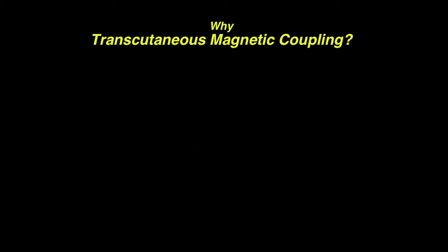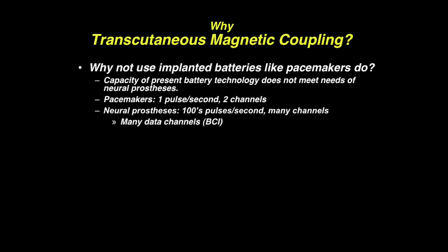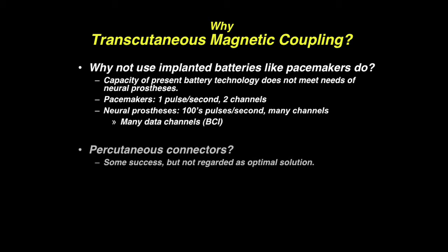Now, why do we have to do this? Why can't we just use implanted batteries like pacemakers do? The problem is that the capacity of present battery technology doesn't meet the needs of neuroprostheses of any kind. And the reason for this can be seen just by looking at numbers. Pacemakers typically will pace about 1 pulse a second, maybe a couple of channels. Neural prostheses, in order to communicate with the nervous system, may have hundreds of pulses per second and many, many channels or many, many output data channels, and the power that would be in a pacemaker battery would simply be exhausted too quickly. So some people have proposed and even implanted percutaneous connectors.